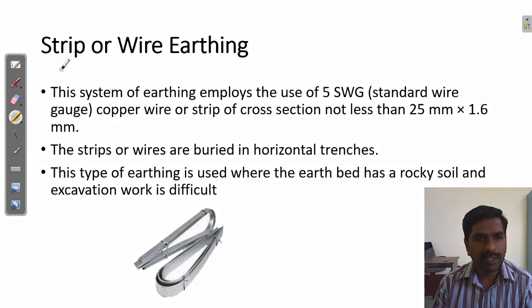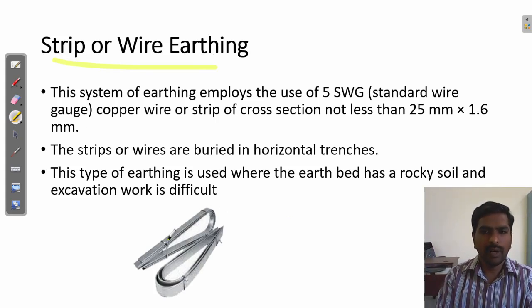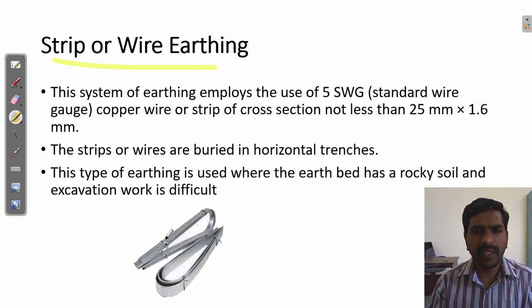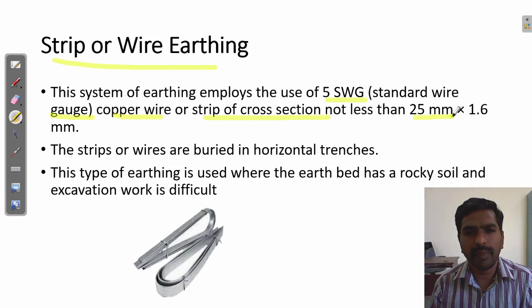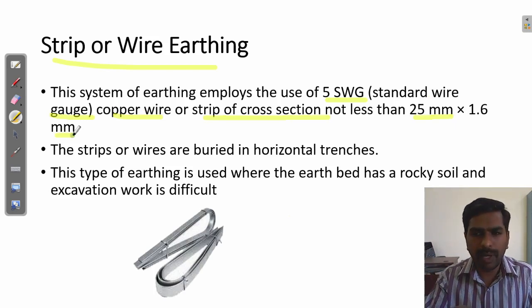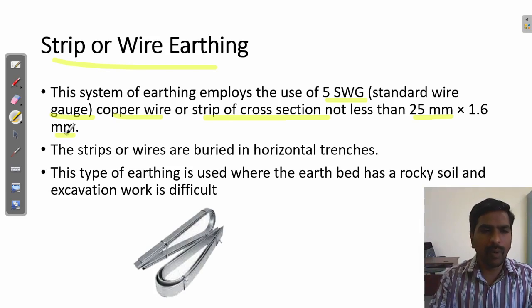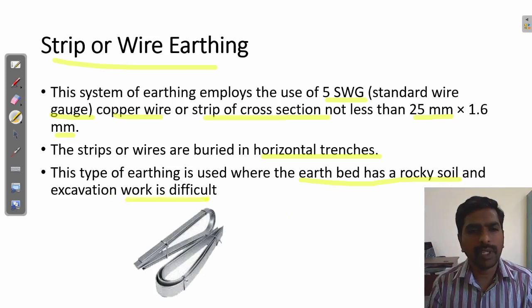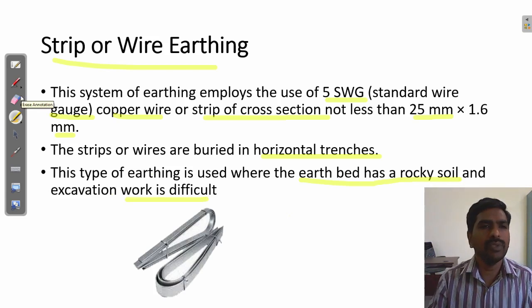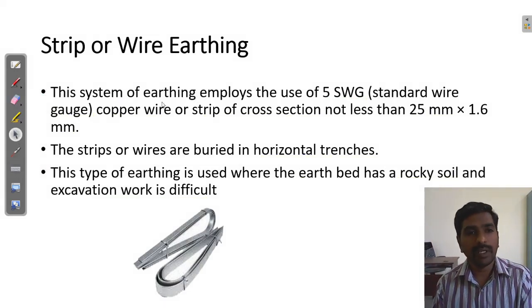Another method is called strip or wire earthing. This is used in rare cases. They use a steel strip or 5 SWG (standard wire gauge) — a copper strip of cross-section 25 millimeter width and 1.6 millimeter thickness. This strip is buried in the land. The strip or wire is buried in a horizontal trench. This type of earthing is used where the earth bed is rocky soil and excavation work is difficult — where it is not possible to dig deeply, then strip earthing is used. Previously silver was used instead of copper.